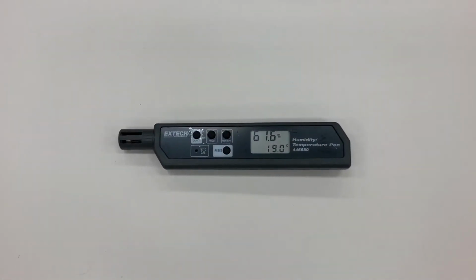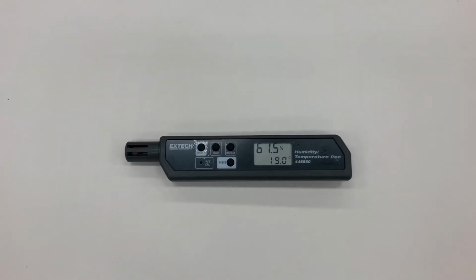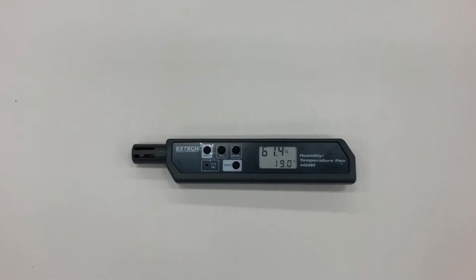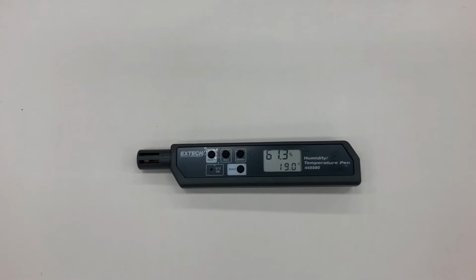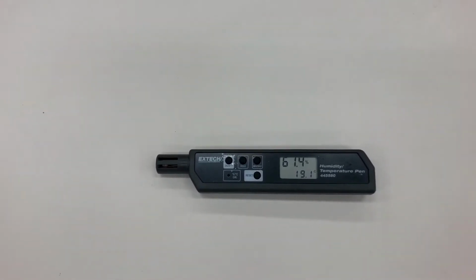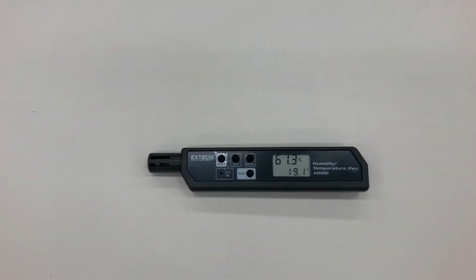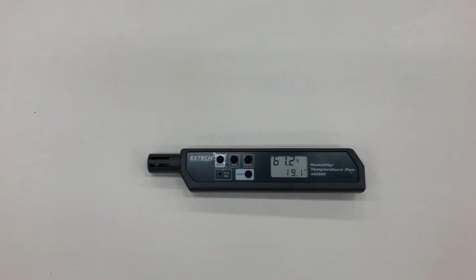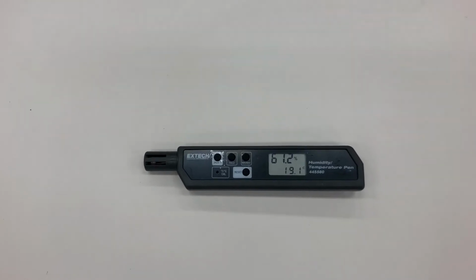For the thermal environment, we have a few tools that we're going to be using in the lab. First off, we have this relative humidity / temperature pen. And when we're looking at relative humidity, it's a hygrometer that's going to measure that. Low humidity is about 20%, whereas high would be 70%. We could also look at dry bulb temperature, and that's going to examine ambient heat or non-radiant heat, and that's usually going to be measured with a shielded thermometer.